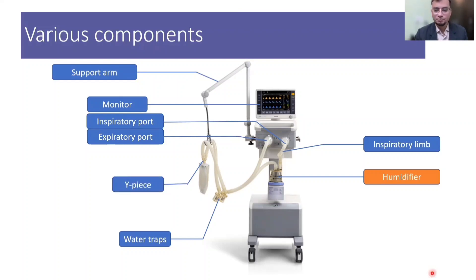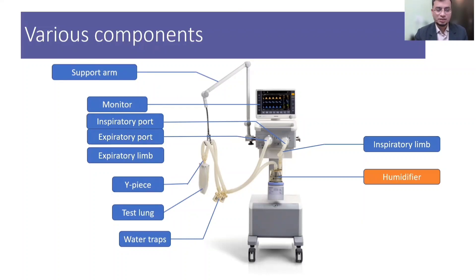The gases are delivered to the patient through a Y-piece connector, and then through an airway device the gases are delivered to the patient's lung. When we want to check the ventilator functioning before connecting to an actual patient, we can connect it to the test lung. From the patient, gases go back to the ventilator through the expiratory limb and then through the expiratory port.